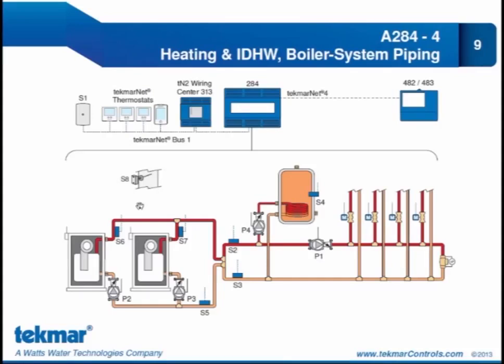And we can connect a vent sensor to the 284, and we can use that sensor to monitor vent temperatures. We can also select a limit, so that if the vent temperature were to rise beyond that limit, we would shut the system down. So again, another new feature for the 284 is the option of connecting a vent sensor for monitoring purposes and for limiting purposes as well. You can see the 284 here is connected to a gateway control. It could be a 482 for home automation, or the 483 to allow the user to remotely monitor and adjust thermostats.